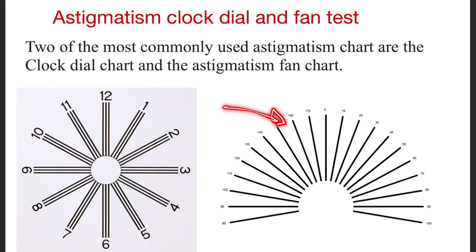So this astigmatic fan chart is going to give you more accurate results of the axis compared to the clock dial chart where the angular difference between two numbers is 30 degrees.